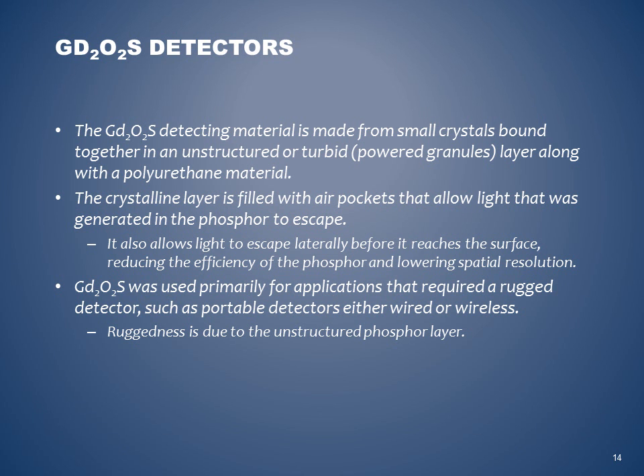The Gd2O2S detecting material is made from small crystals bound together in an unstructured, powdered granule layer along with a polyurethane material. The crystalline layer is filled with air pockets that allow light that was generated in the phosphor to escape. It also allows light to escape laterally before it reaches the surface, reducing the efficiency of the phosphor and lowering spatial resolution. Gd2O2S was used primarily for applications that required a rugged detector, such as portable detectors, either wired or wireless. Ruggedness is due to the unstructured phosphor layer.